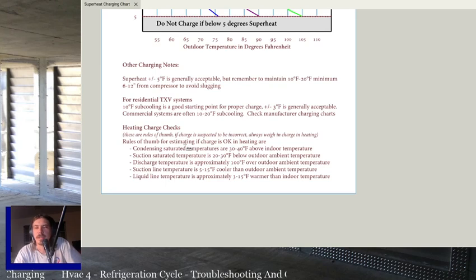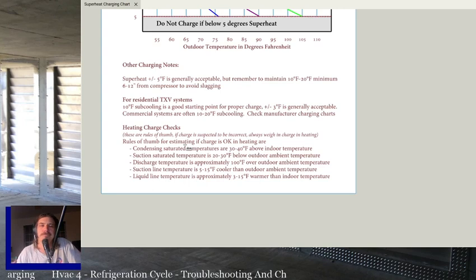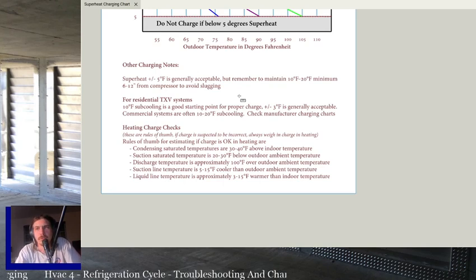Obviously, you want to try and diagnose any other issues, but if the system worked last summer, everything seems pretty good, but it had a slow leak or something, and you want to check and make sure the charge looks all right in heating. A lot of manufacturers will have heating charge charts. You should use those because they're going to be more accurate than this, but these are generally pretty close. And if you paid attention in that video on what is normal, these things should all make sense to you. So the rules of thumb for estimating if charge is okay in heating are: condensing saturated temperatures are 30 to 40 degrees above indoor temperature.